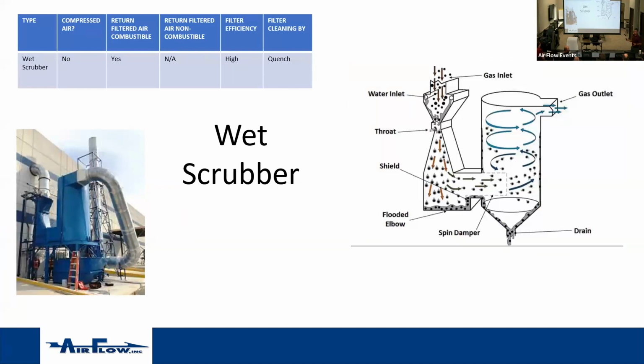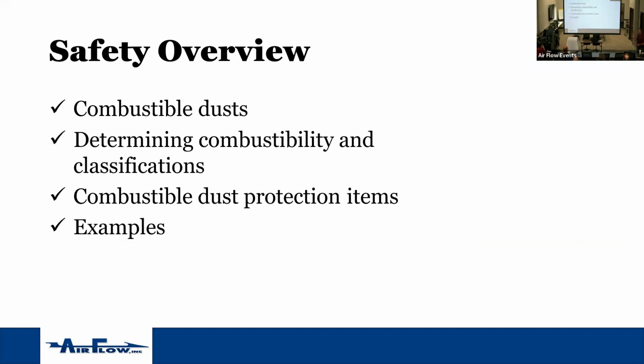Wet scrubber, same type of theory. Your dirt will come in. Sometimes it's in the form of a gas, where you want to actually wash the gas, keep it from being ejected out, or particulate. This particular wet scrubber, there's multiple different ones. There's a packed bed scrubber, there's a sump-based scrubber. It'll come through a series of either packed media or through a sump where it forces the particulate to hit the water itself or a spray nozzle, which will wash the air. And in theory, all of this stuff drops out the bottom, and clean, moist air comes out. It's going to be high humidity. So basically sending it through a mist. And when it comes out of there, it'll be in a vaporized form, but you'll want to find a way to mitigate that moisture if you're going to put it back in your building.